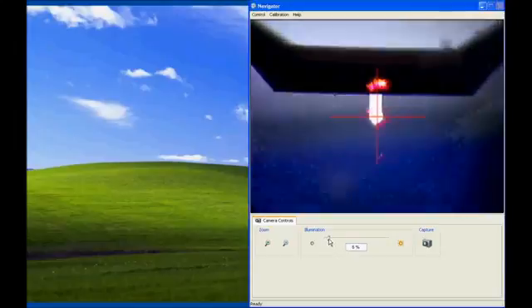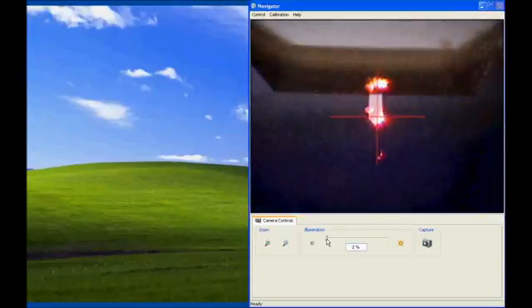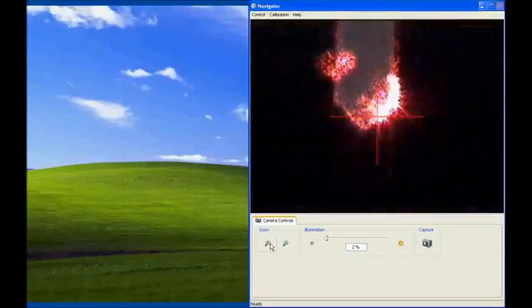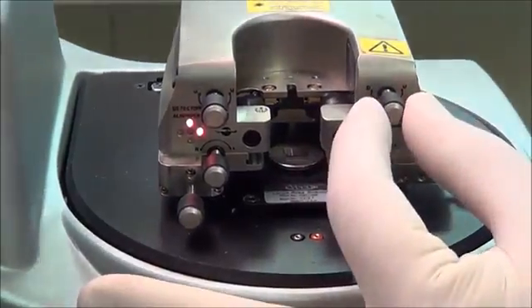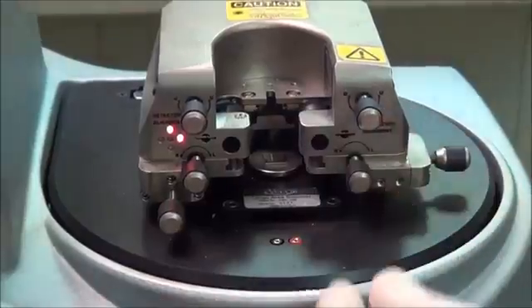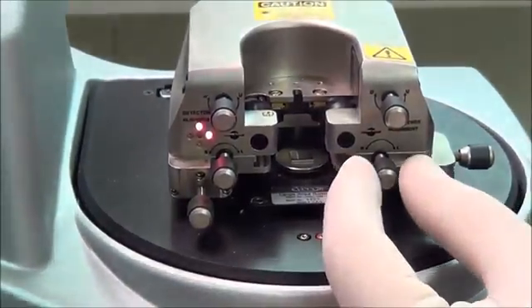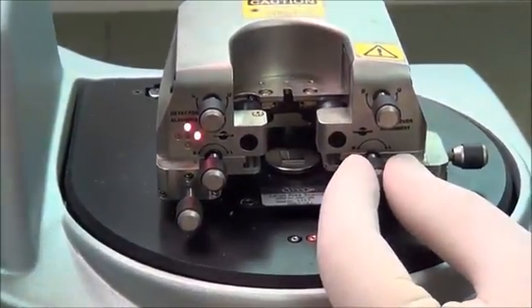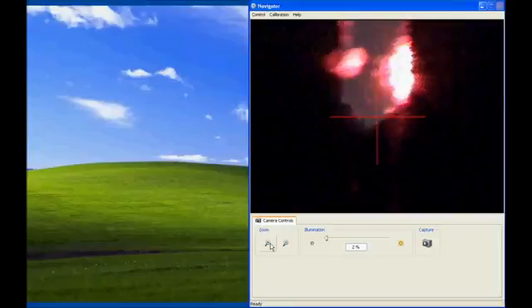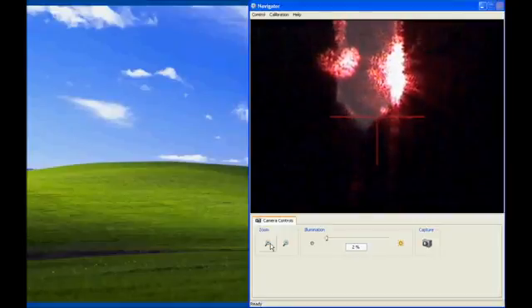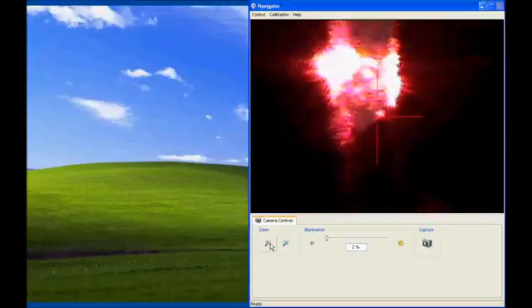Now we're ready to align our laser, so we'll lower the illumination to see the laser better and zoom in on the cantilever tip. On our stage, the upper right knob is for shifting the laser up and down, while the one below is used for side to side. We use these controls to adjust the laser spot on the end of our cantilever. Note that the laser spot is as wide as the cantilever itself and where we place the spot.